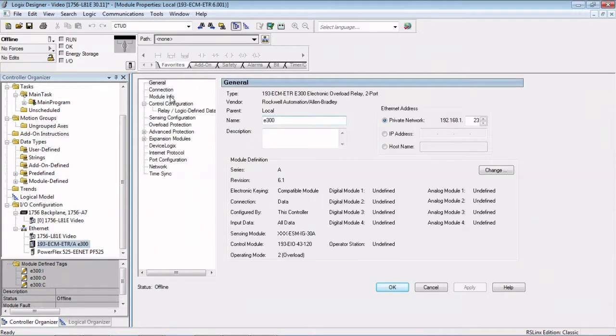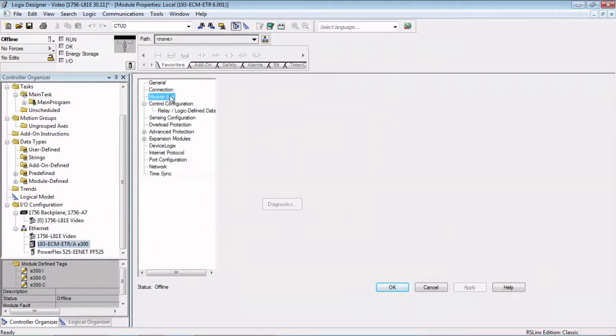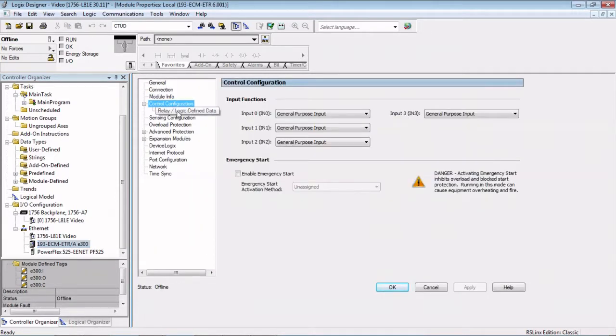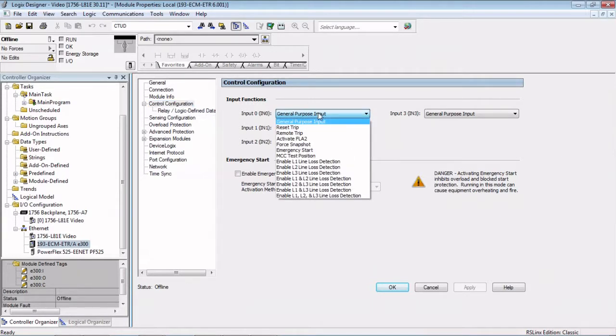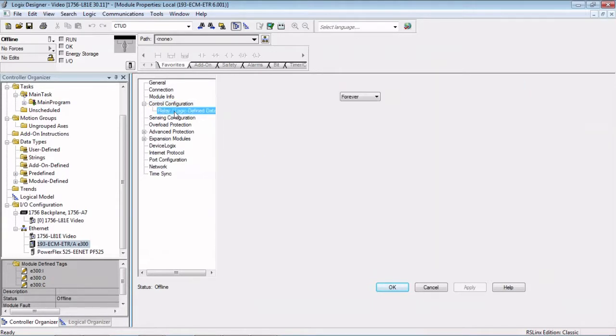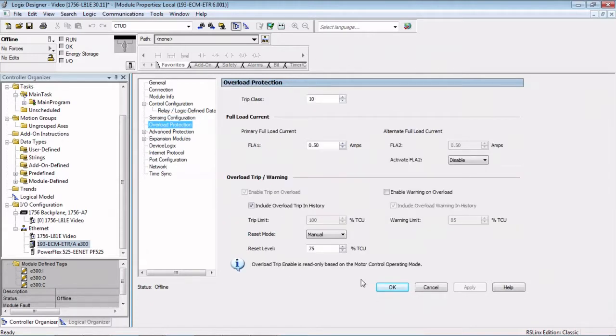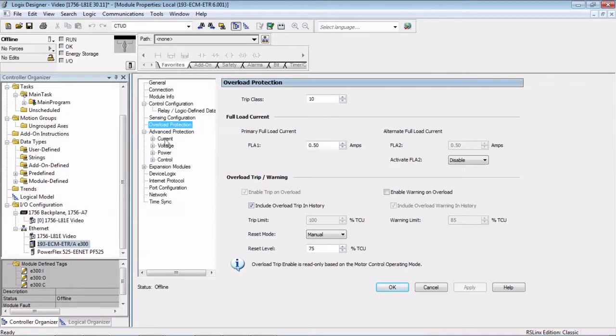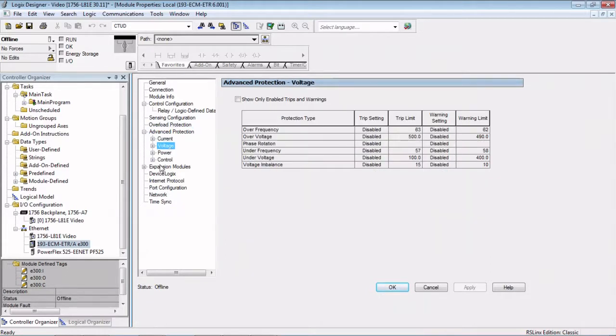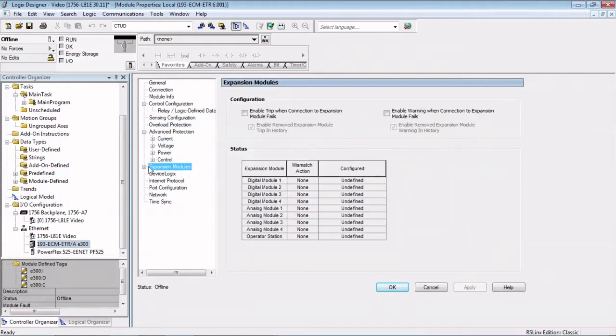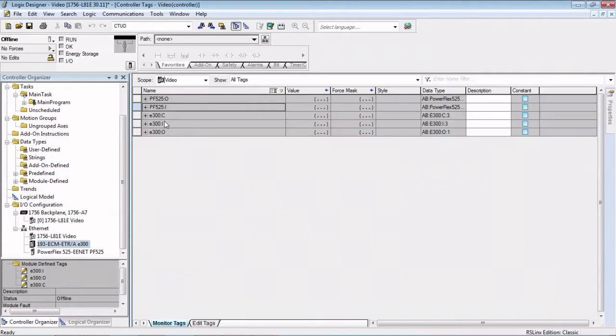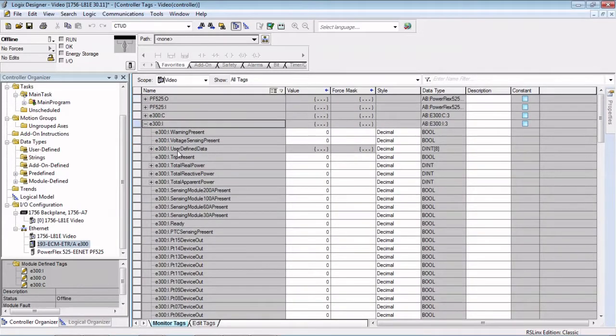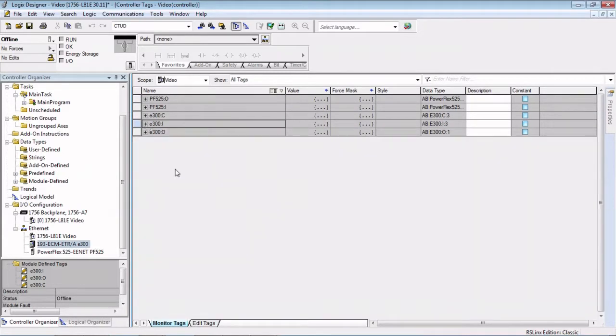Here it creates our tags for us. But there's a lot of other configuration that goes on with the E300 that, again, we don't have to open up a different piece of software for. We can come in and set up that overload all through here. We don't have to open up networks or a third-party piece of software. All of it can be done right through Logix. And again, it creates our tags for us so that we don't have to worry about writing those message instructions.